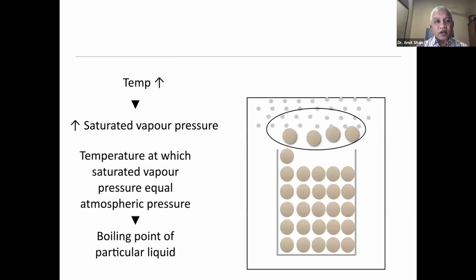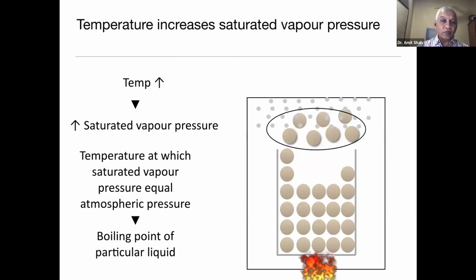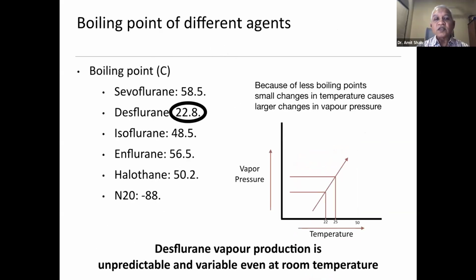Okay, so we have seen that when temperature increases, there is an increase in the saturated vapor pressure, and the temperature at which the saturated vapor pressure equals the atmospheric pressure is the boiling point. Now, the boiling point of desflurane is just 22.8. At the operation room pressure or any other atmospheric pressure, the moment temperature goes slightly up or down, the vapor production varies. It becomes unpredictable and variable even at room temperature because of the very low boiling point. The other agents have a boiling point much higher than the room temperature, but the desflurane boiling point is right at room temperature, and a slight change creates a lot of problems.